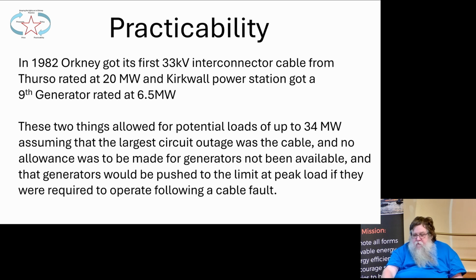In 82, Orkney got its first 33 kV interconnector cable from Thurso, rated at 20 megawatts. And Kirkwall Power Station got a 9th generator at 6.5 megawatts. These 2 things allowed for potential loads of up to 34 megawatts, assuming that the largest circuit outage was the cable. And we always take the largest. If you've got 2 options, you take the largest out. And no allowance was to be made for generators not being available. Generators would be pushed to the limit at peak load if they were required to operate following a cable fault.